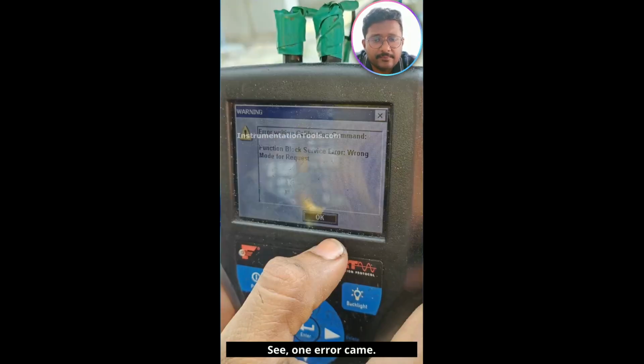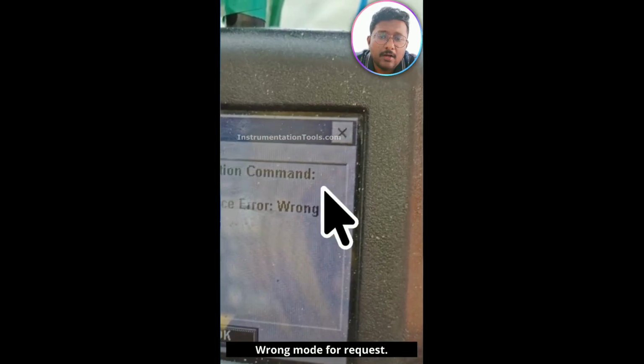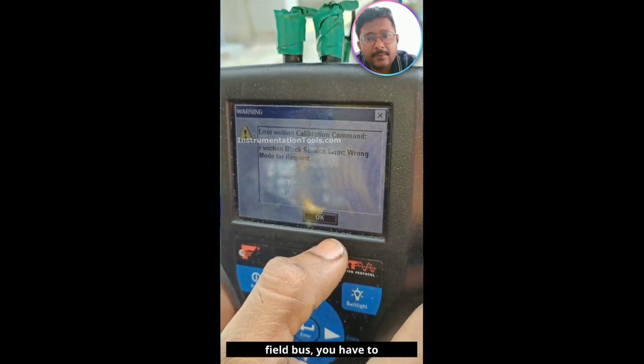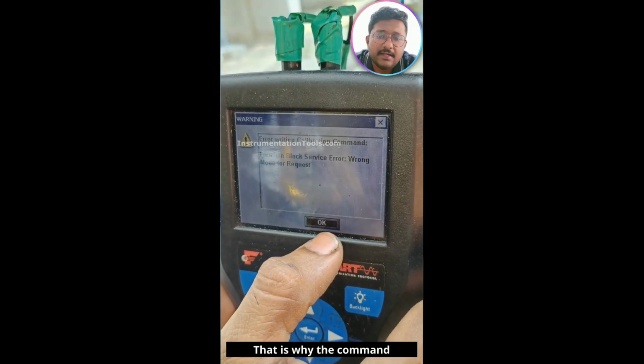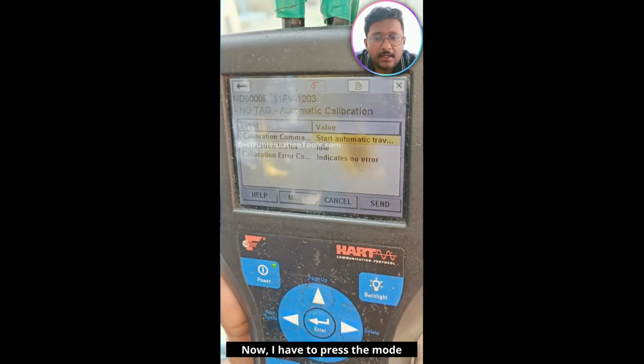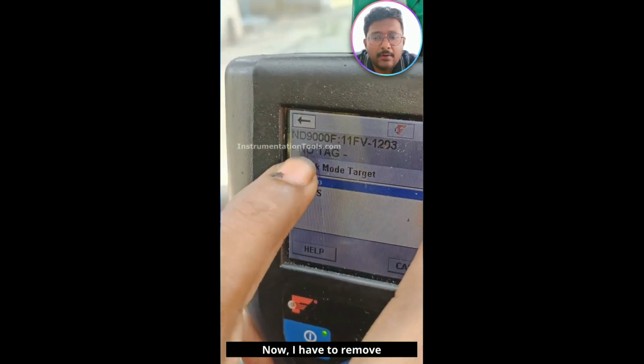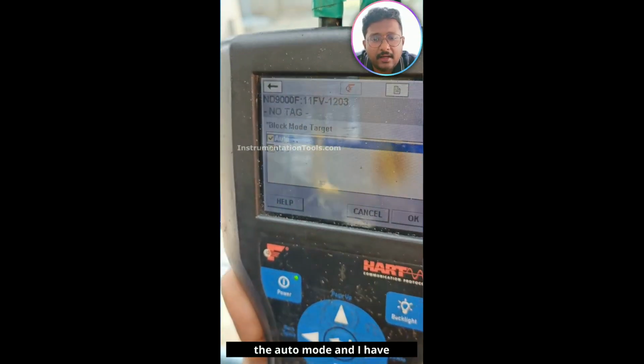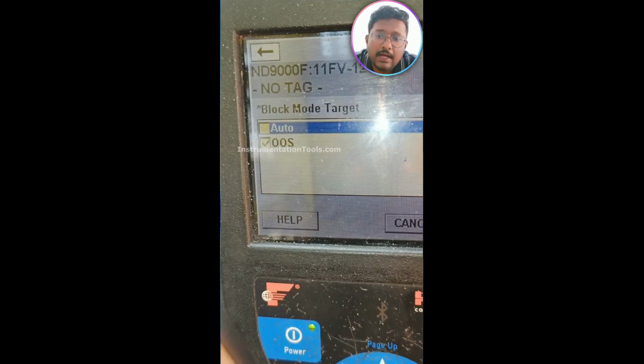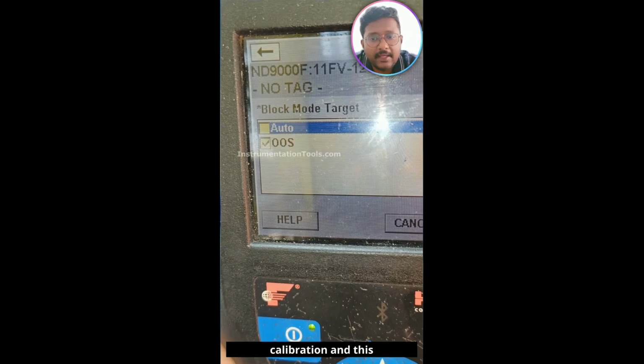See, one error came. What is the error? Wrong mode for request. Whenever you're doing some work in foundation field bus, you have to put that respective block in out of service. That is why the command is not accepting right now. Now I have to press the mode. Now I have to remove the auto mode, and I have to select out of service. Now I will remove the auto mode, and I will select only out of service, because right now I'm doing the calibration and this device or control valve is not available for the operation. Okay, and press OK.